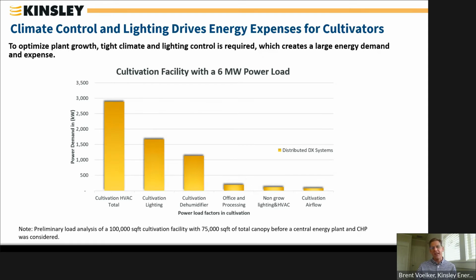So it's imperative that in addition to your considerations of utility power, you also try to get that load down as low as you possibly can. And how we do this is a two-step process, really. The first step has to do with centralizing your utilities by using high efficiency air or water cooled electric chillers. And then you have an opportunity in that system to plug cogeneration in.